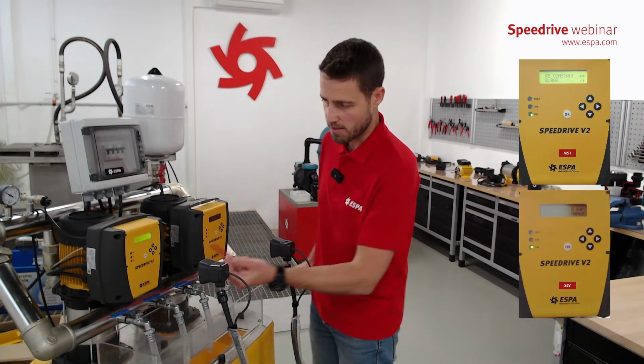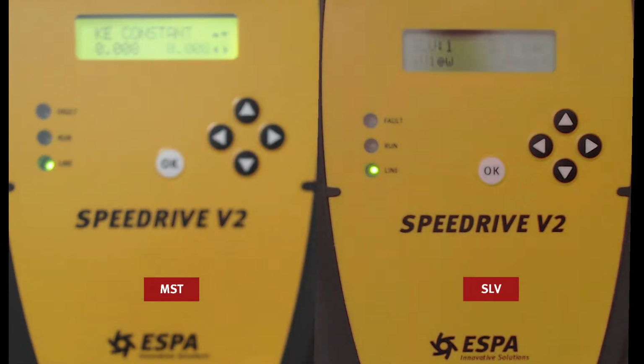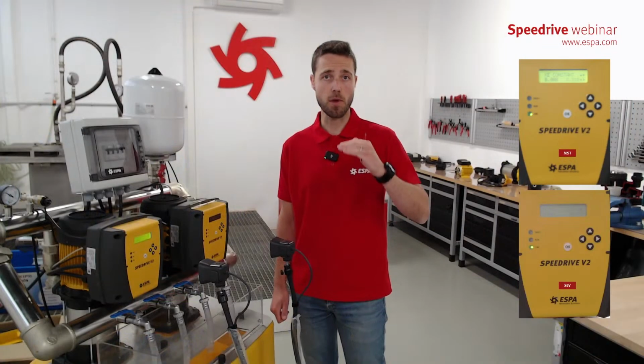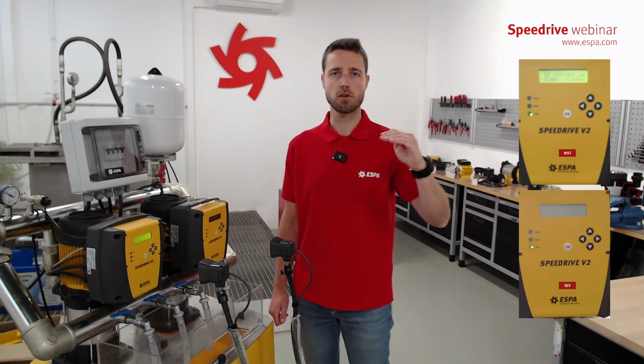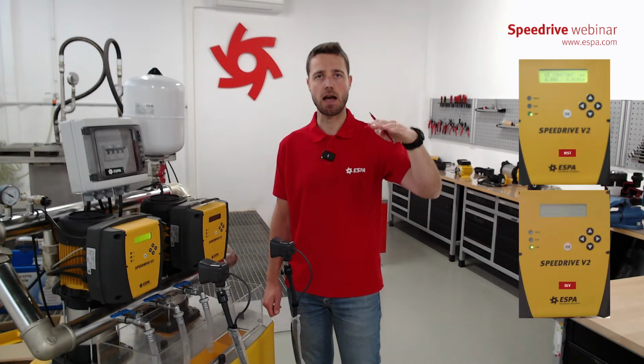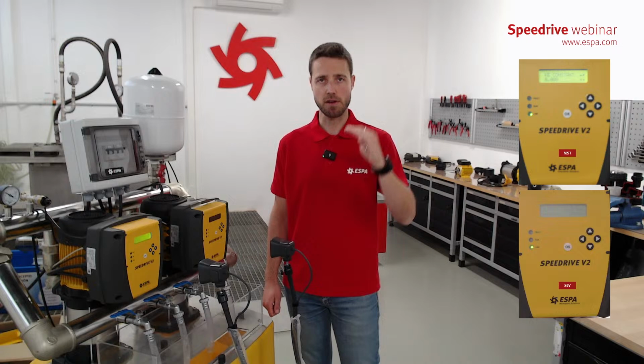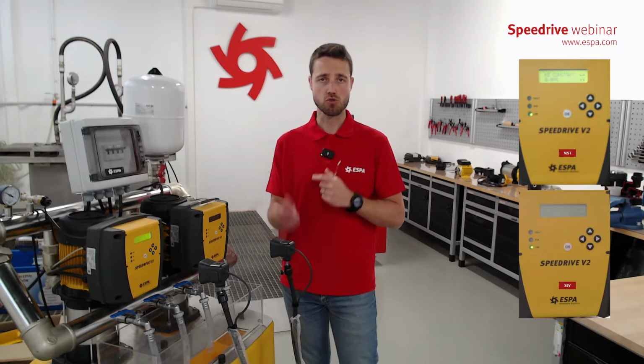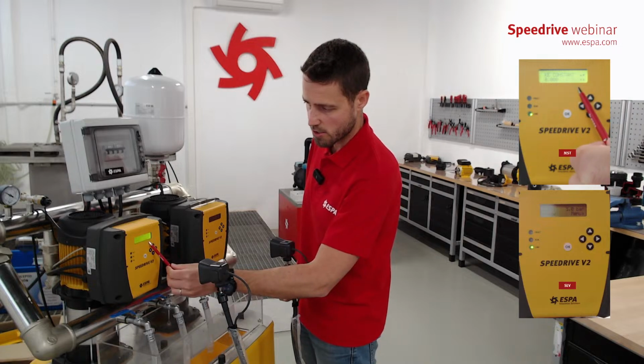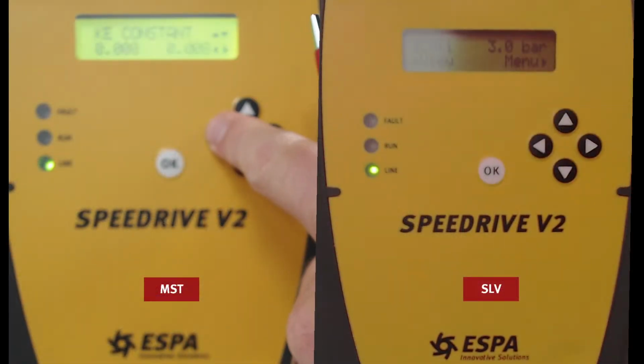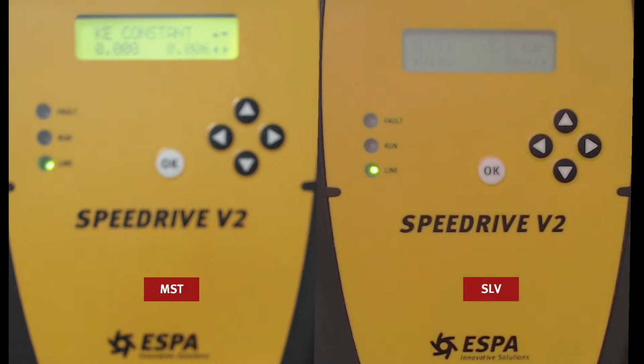And this constant is to indicate how fast we can reach the desired duty point. If we increase the constant, we will approach the duty point faster. But there is a drawback in that if we go too fast to reach the duty point, we can overshoot it and we can have oscillations, and we can have an imbalanced system. Contrarily, if the constant is too little, we will go maybe too slow.